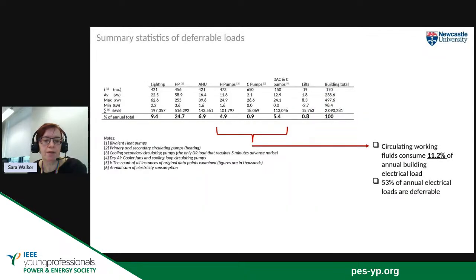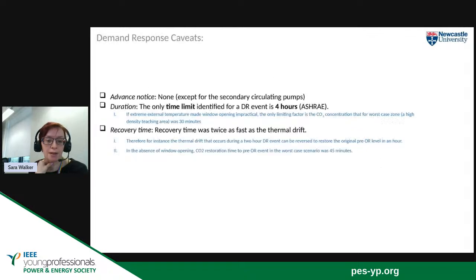So what that means in terms of the different loads. Remember, we said a virtual power plant should have heterogeneous loads. We've definitely got that. We've got lots of different categories of load, and the percentage contribution that they make to the overall building load varies. So that gives us some nice variety to the nature of the loads that we can defer. And essentially, of all of the electrical loads in the building, about half could offer some kind of demand response without interrupting the operation of the building and the thermal comfort of the occupants.